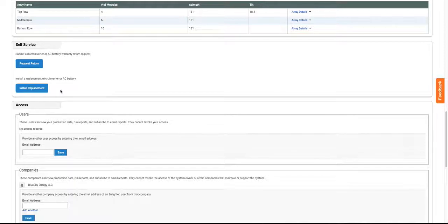The basic process is turning your system off, going up on the roof, removing the PV module, taking care to remove the leads from the PV module to the inverter carefully. Now, keep in mind, if you're doing this during the daytime, while it's sunny, there will be DC voltage. So the metal contacts are well inside of the connectors, so they're generally not a concern, but just be mindful of that. And then you're just pulling off the old inverter and installing a new one in similar fashion to what's up there now, putting the module back in place.